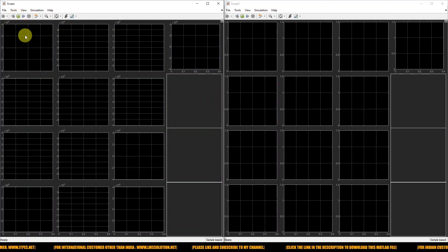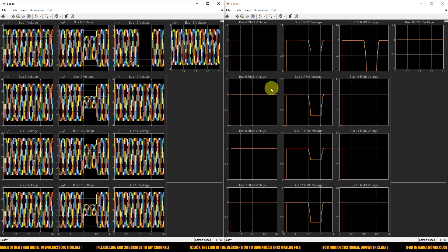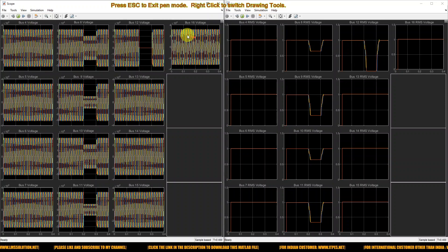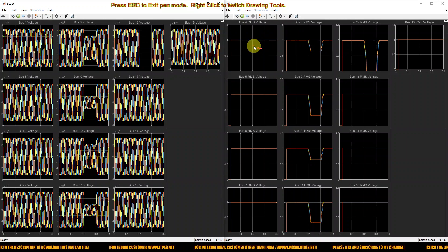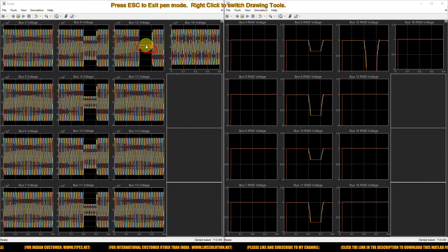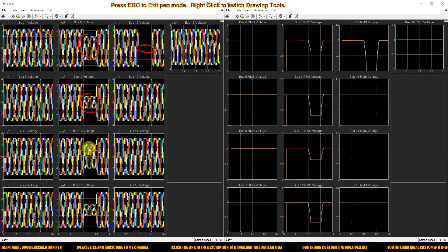The model is executed to measure bus voltage from bus 4 to 16 — buses 4, 5, 6, 7, 8, 9, 10, 11, 12, 13, 14, 15, and 16. The fault is created at bus number 12, so the voltage at bus 12 drops to zero. Buses 8, 9, 10, and 11 also show voltage sag.